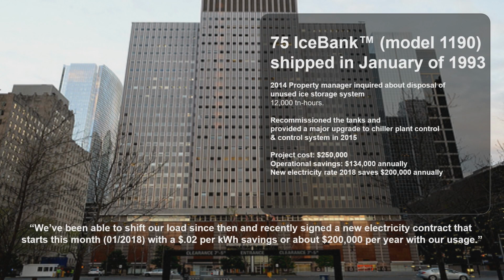The size of the thermal storage system in battery terms was just under 1 megawatt. The building had changed ownership a few times, and electric deregulation made it appear that the value of this thermal battery asset was no longer viable. The third-party electricity supplier had portrayed the electricity contract as a flat rate, so using the tanks would cost the owner more money. Upon further review of the energy charges, like Evan reviewed with us, the rate was not flat. It was determined that lower energy costs could be realized by operation of the thermal battery system.